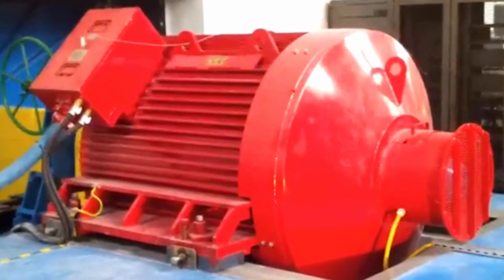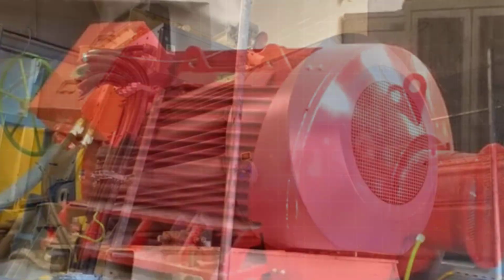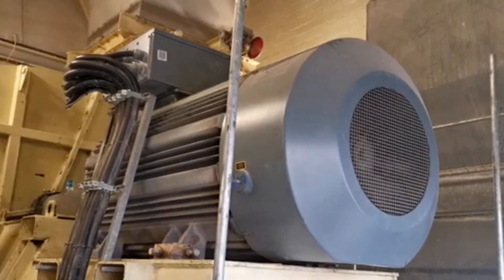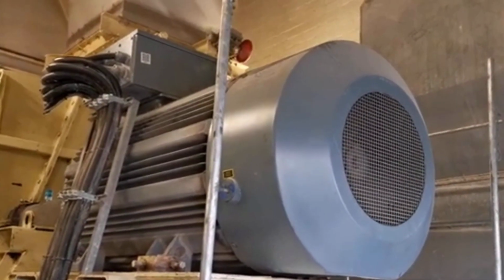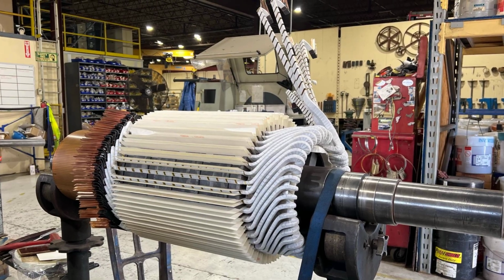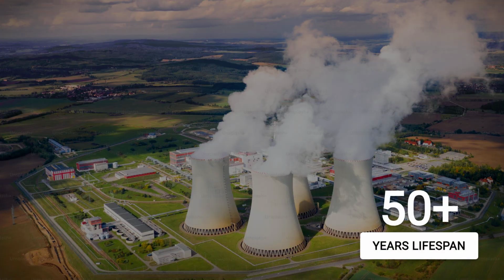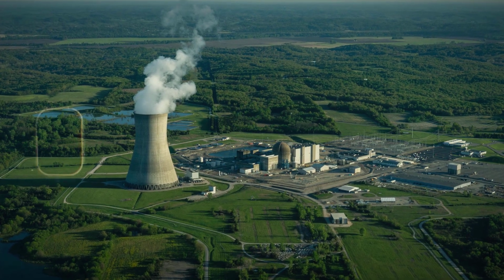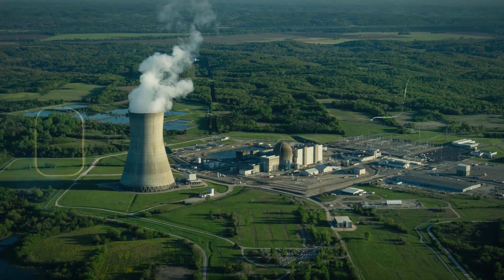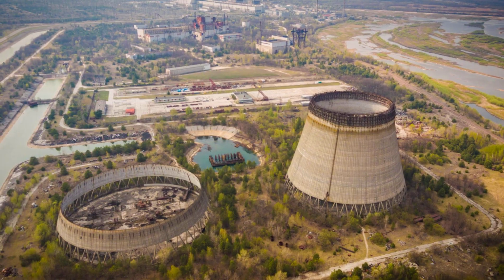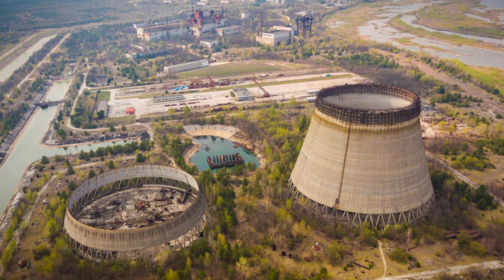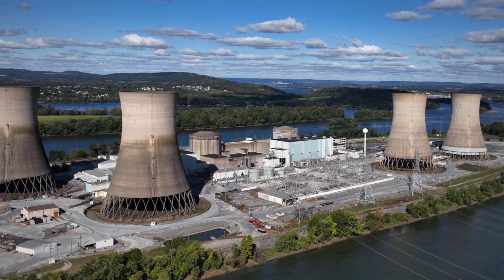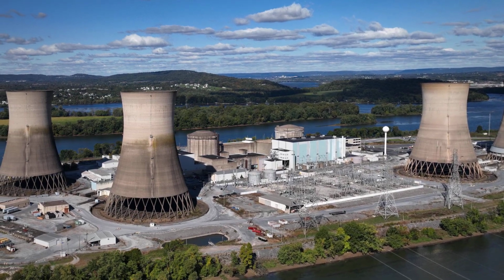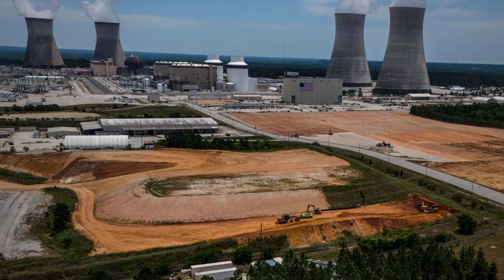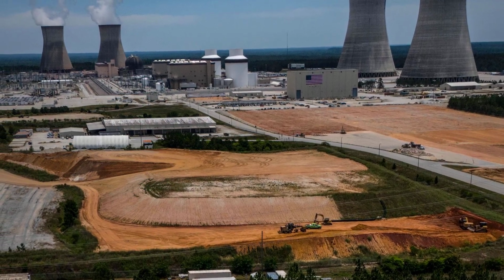The long-term operational savings, primarily from avoiding the energy consumption and maintenance of large fans, often outweigh the higher initial construction costs of natural draft towers. This is particularly true for nuclear plants, designed with operational lives of 50 years or more, allowing for cost amortization over extended periods. These facilities are also typically built in more remote locations, where land is cheaper and height restrictions are less stringent, making it feasible to construct such massive structures solely for cooling.